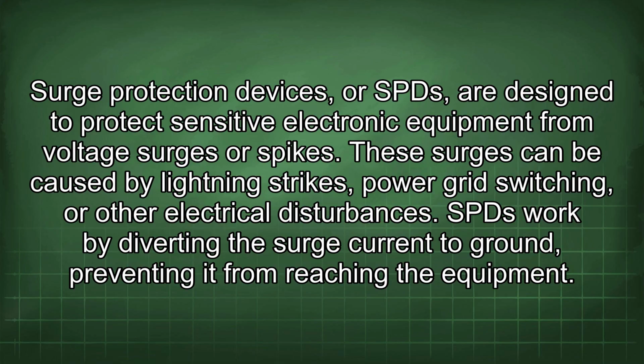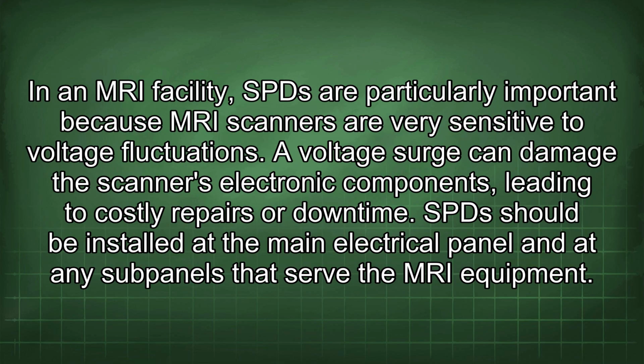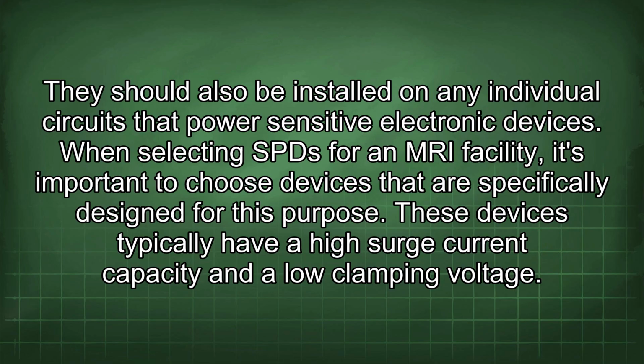SPDs work by diverting the surge current to ground, preventing it from reaching the equipment. In an MRI facility, SPDs are particularly important because MRI scanners are very sensitive to voltage fluctuations. A voltage surge can damage the scanner's electronic components, leading to costly repairs or downtime. SPDs should be installed at the main electrical panel and at any subpanels that serve the MRI equipment. They should also be installed on any individual circuits that power sensitive electronic devices.